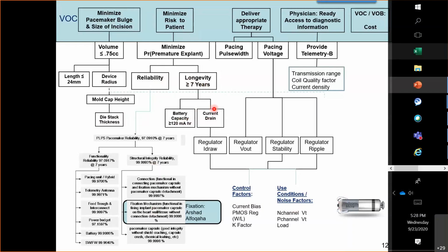Then we had to make sure that this device actually provides therapy for pacing the heart, and that requires a requirement on the pacing voltage. That flowed down to requirements on the regulator that set that pacing voltage, and that flowed down to requirements on the use conditions and the control factors, the noise factors and the control factors, which you see down here, and I'll mention that in a moment. And then the physician wanted ready access to diagnostic information, so that put a requirement on the antenna, which I'll show you an example of in a little while.